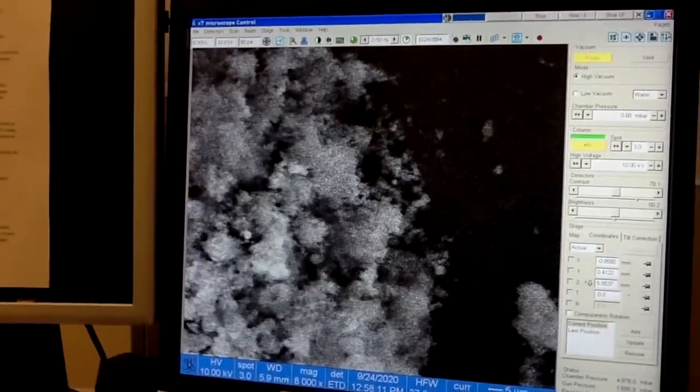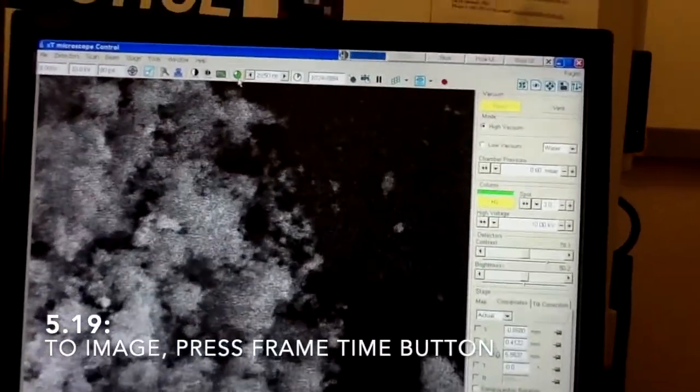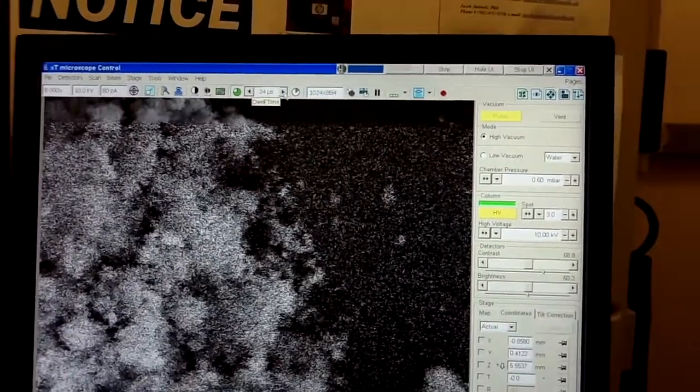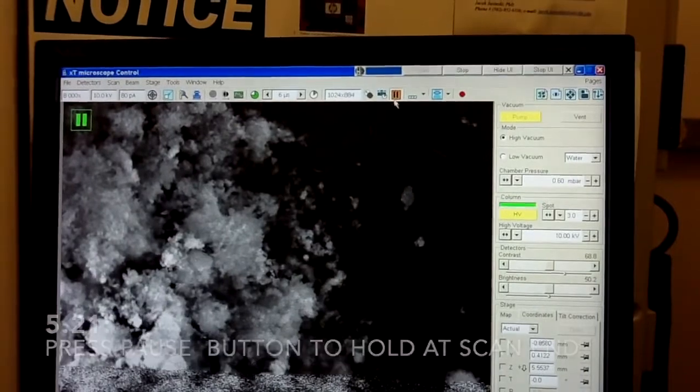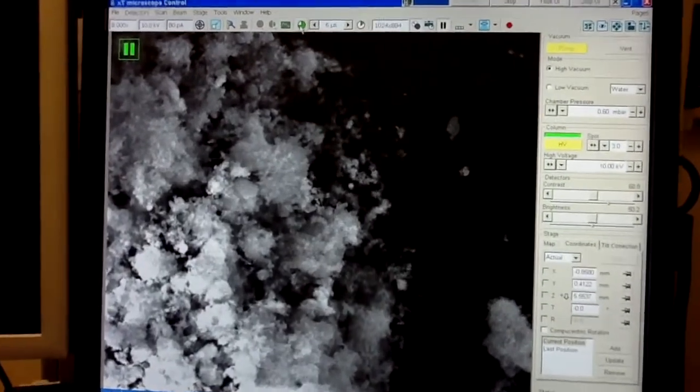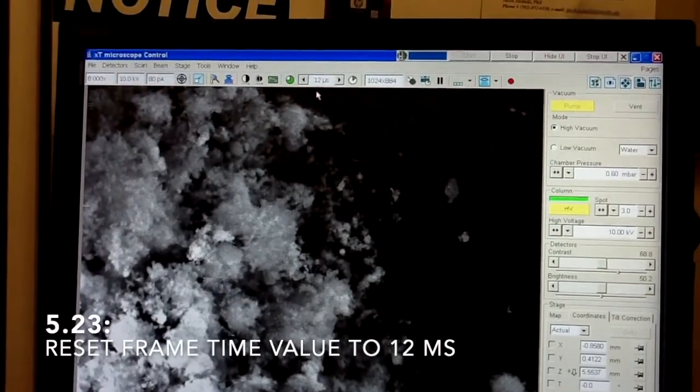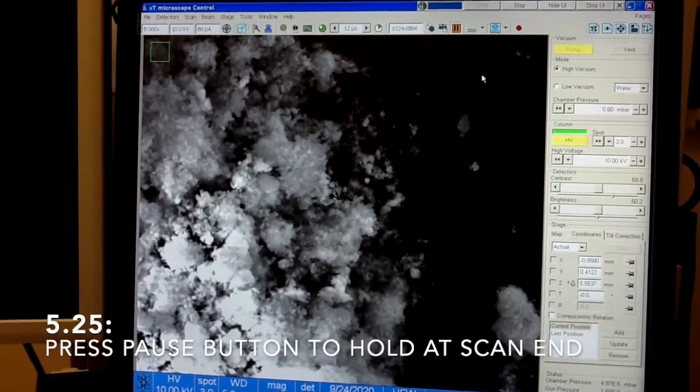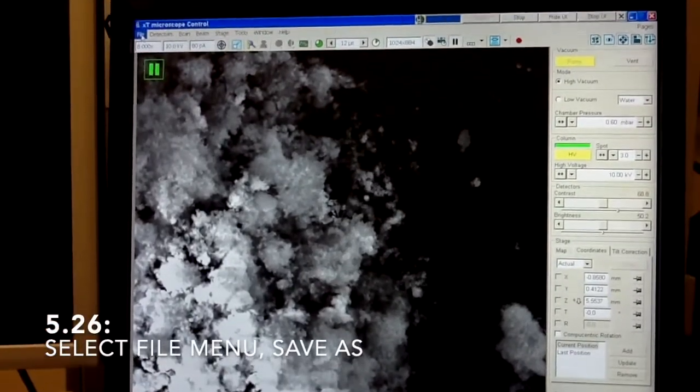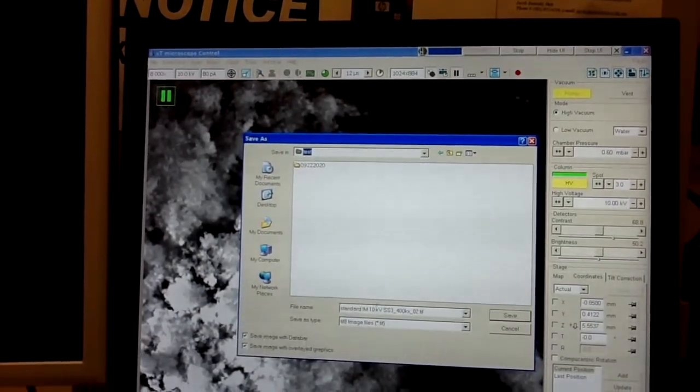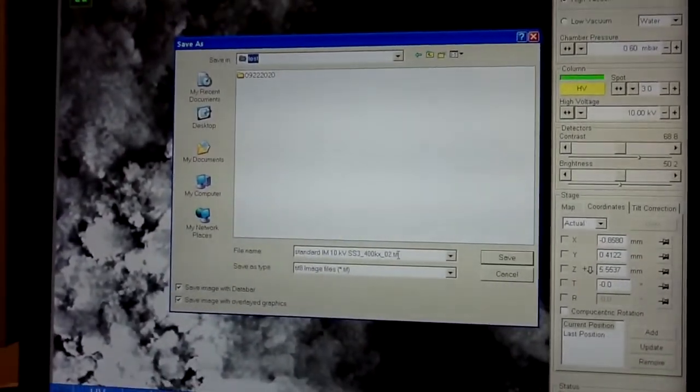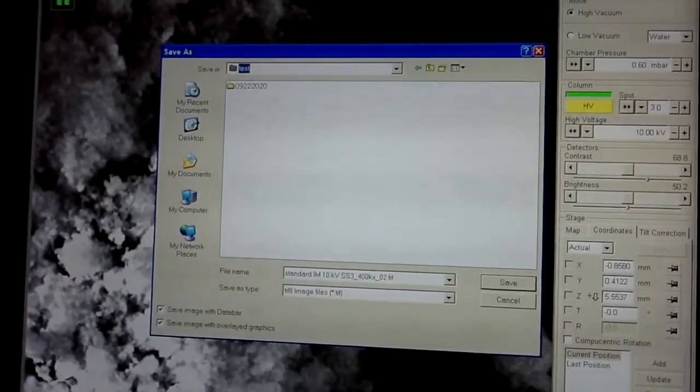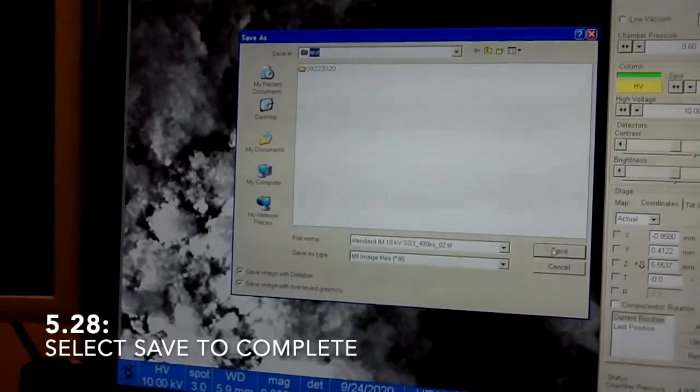If, let's say, the magnification 8000, which we have right now, is what you are looking for, then you just press this button, which will slow down the refresh. And I recommend using 6 microseconds. And then, make sure that you press the pause button, then it will stop at the end. So, if the image is too noisy, you can do this, you can release the pause button and maybe record it at 12 microseconds. And then, of course, while this is scanning, make sure that you press the pause button, because this will stop. After you do this, you can save your image. Give the sample name, the parameters. I like to add the voltage, the spot size, the magnification. But it's your image, you decide what you put it. But you will always on your image have this information anyway. But this is a good way to put it into the name of the file, then you know what's exactly in this file.